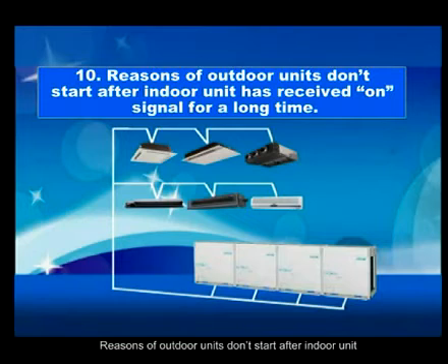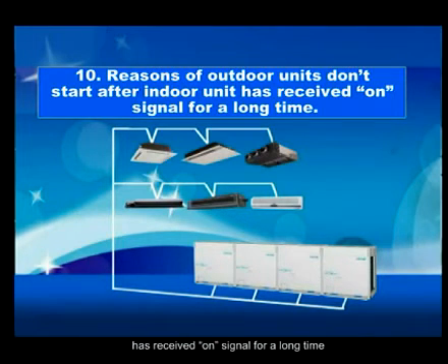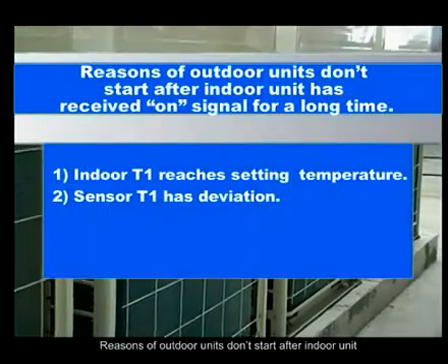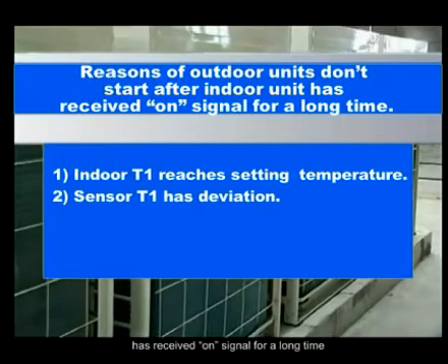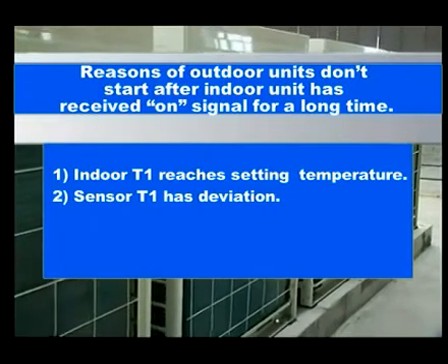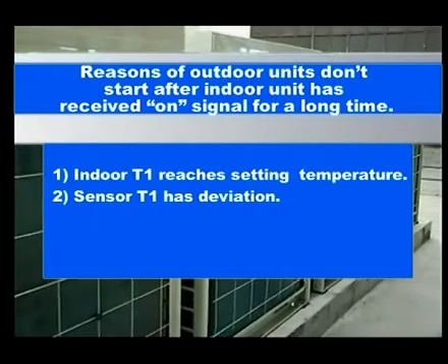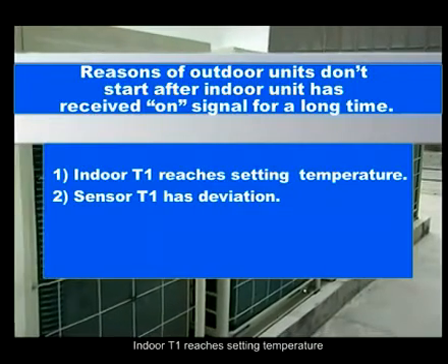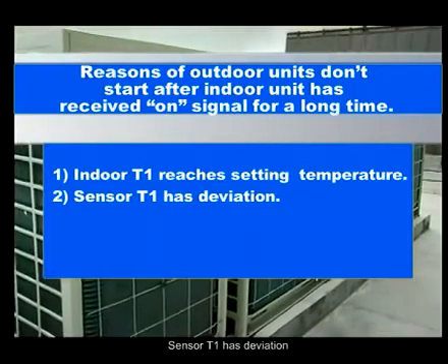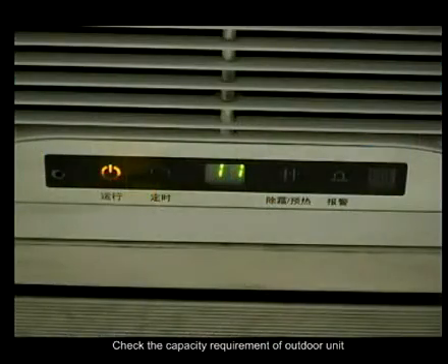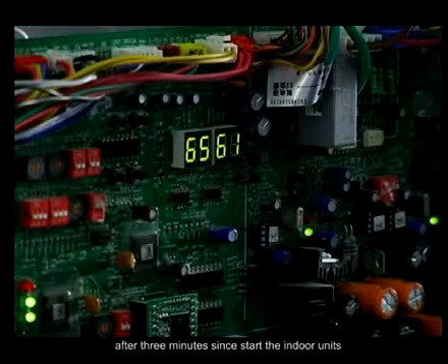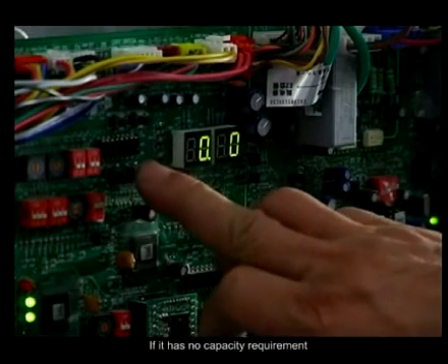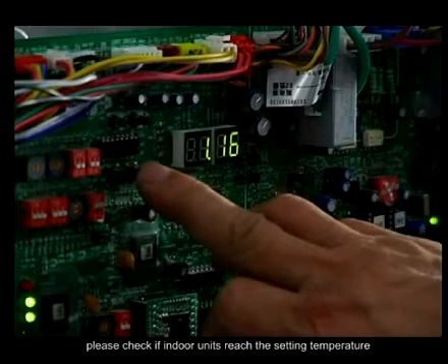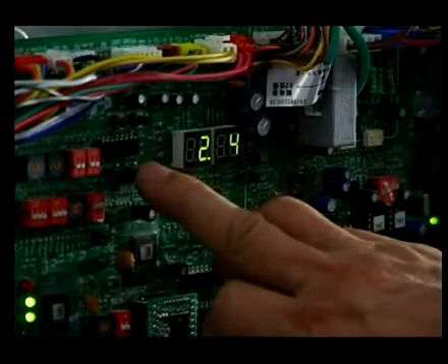Reasons why the outdoor units don't start after the indoor unit has received the on signal for a long time. Indoor T1 reaches the setting temperature, or sensor T1 has deviation. Check the capacity requirement of the outdoor unit 3 minutes after starting the indoor units. If there is no capacity requirement, check if the indoor units reach the setting temperature.